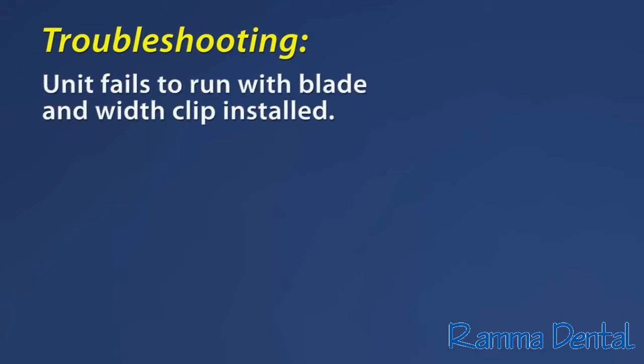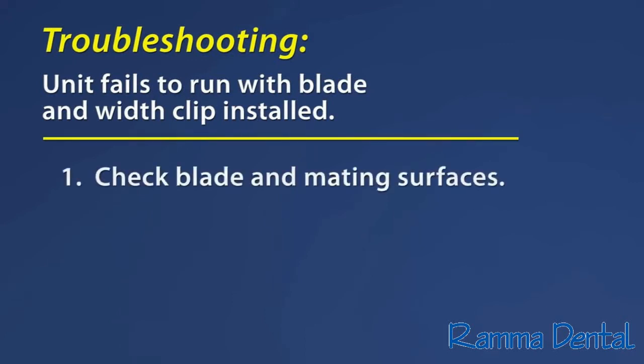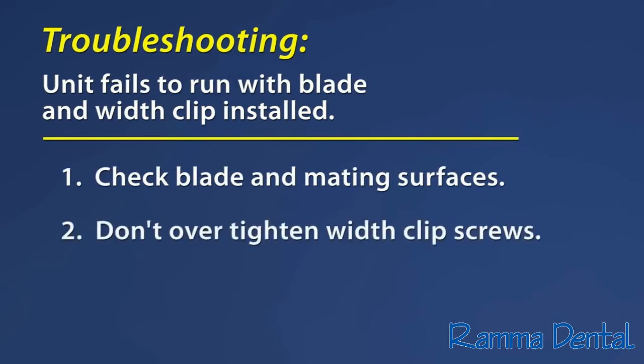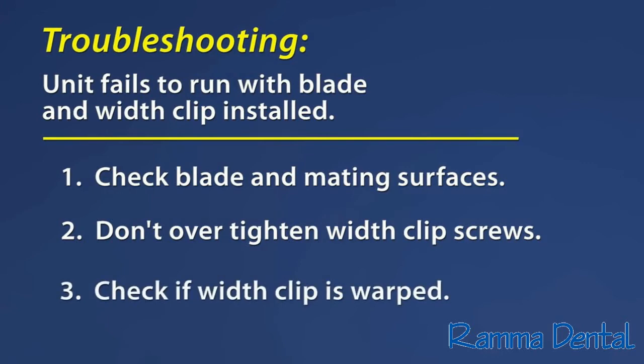The unit fails to run with the blade and width clip installed. 1. The blade and its mating surfaces of the dermatome are to be free of lint or other foreign objects which may hinder free movement of the blade. 2. Use only the supplied screwdriver in order to avoid over-tightening the width clip attachment screws. 3. Check the condition of the width clip for distortion, especially flatness, and rough edges.